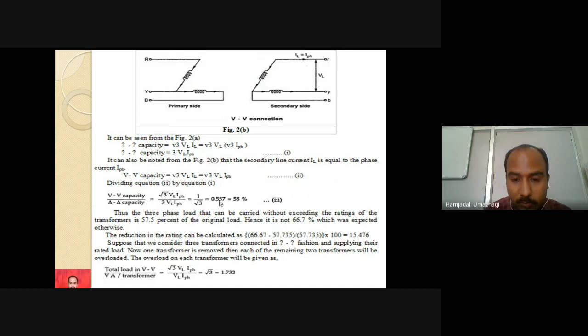So here it is, 0.577. This is not 5, make this as 7. Thus, the three-phase load that can be carried without exceeding the ratings of the transformer is 57.7% of the original load. Suppose if I connect 100 kilowatt, then I should reduce it to 57.7 kilowatt if it is VV connection. Hence, it is not 66.7%, which was expected otherwise.